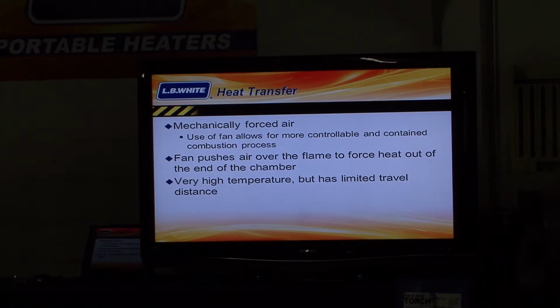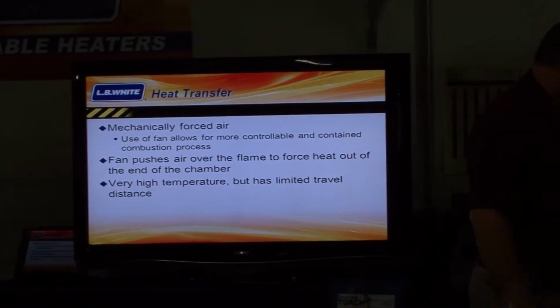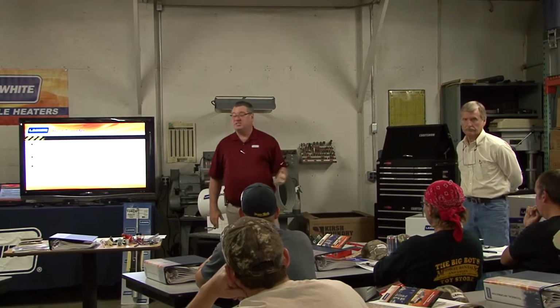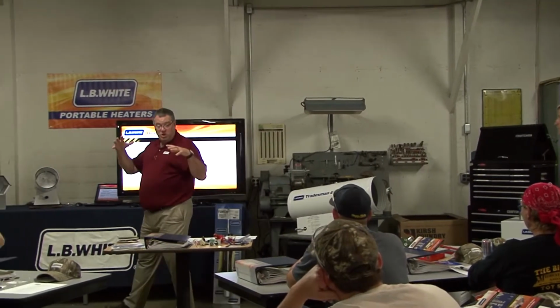So what starts as this much intense heat stretches out and then starts to dissipate up into your environment. With this unit, you're probably standard 12 feet out, smaller units, 6 to 8 feet out. You're going to come out and then naturally it's going to dissipate because it's such an intense temperature. Higher the temperature, the quicker it's going to rise. So with these units, you're putting out intense heat, you're able to convert those BTUs very quick into your environment. However, they're typically for smaller spaces because you can dissipate that heat quicker.